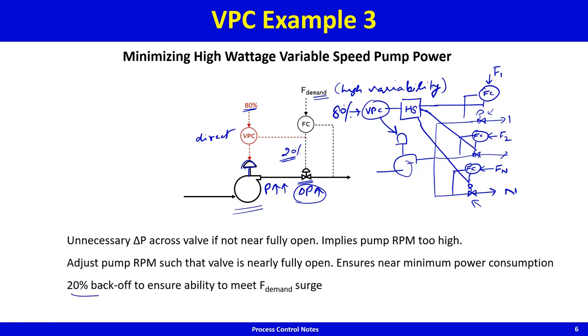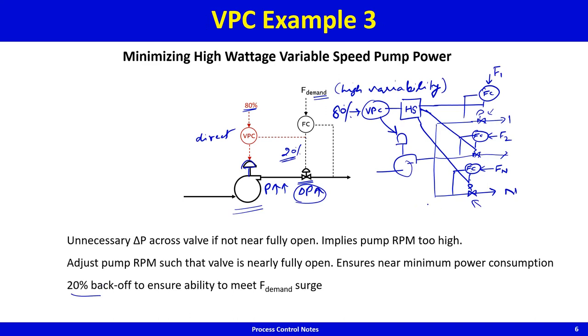This 20% back-off again ensures the ability to meet any surges in downstream customer demands, so customers can immediately get more flow. This is an example of valve position control combined with selective control.